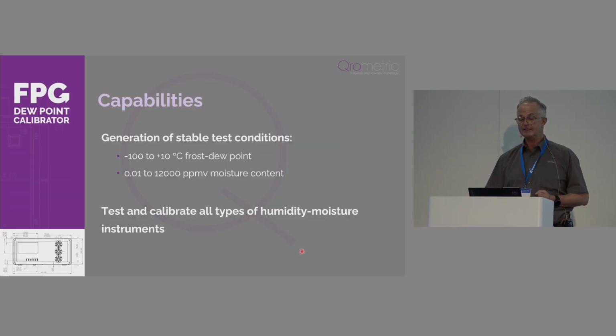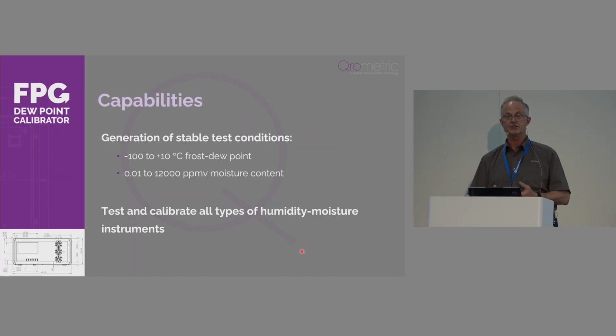So the capabilities are relatively straightforward. We can generate test conditions from -100 to +10 frost dew point, which is equivalent to 0.01 to 12,000 ppmv of moisture content. And with this capability, you can test and calibrate any type of instrument. So it doesn't matter who the brand, manufacturer, or type is, you can calibrate it with the FPG.